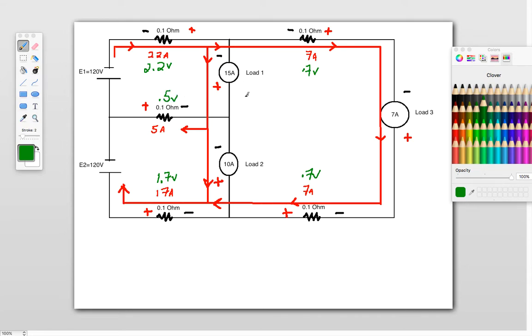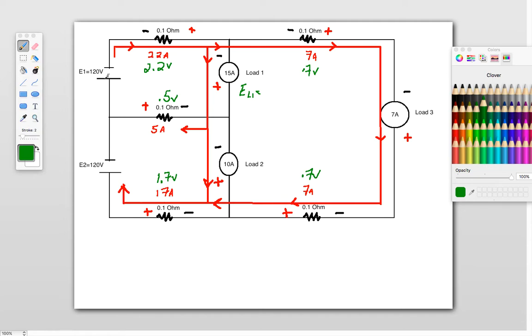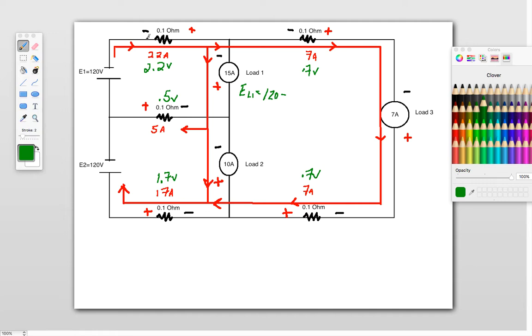So now when calculating our loads, what we do is we say, my voltage at load 1 is going to be equal to, well, what you do is you start with your 120 and you either add or subtract based on the direction of your current lines. You just follow your current lines. You either add or subtract based on what you come to first. So I've got 120 volts. I'm coming to this first. So I start with 120 minus, because I have a negative there, this 2.2 volts.